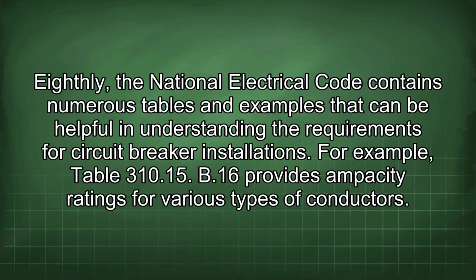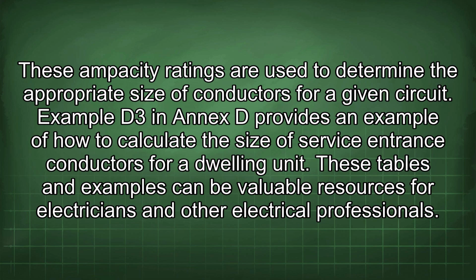Eighthly, the National Electrical Code contains numerous tables and examples that can be helpful in understanding the requirements for circuit breaker installations. For example, Table 310.15(B)(16) provides ampacity ratings for various types of conductors. These ampacity ratings are used to determine the appropriate size of conductors for a given circuit. Example D3 in Annex D provides an example of how to calculate the size of service entrance conductors for a dwelling unit. These tables and examples can be valuable resources for electricians and other electrical professionals.